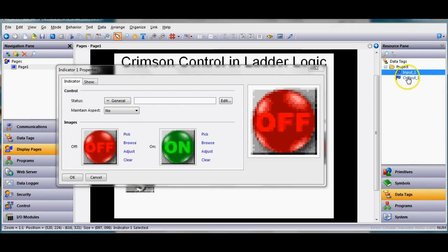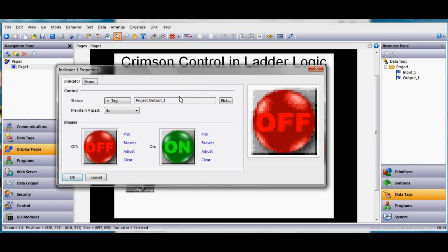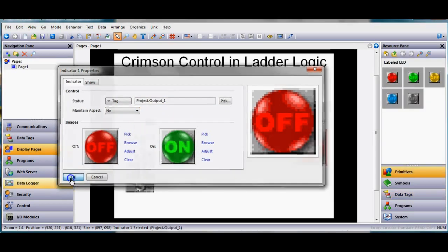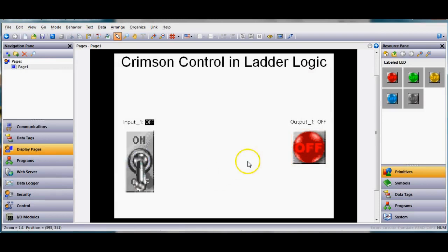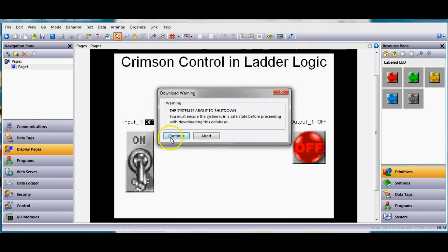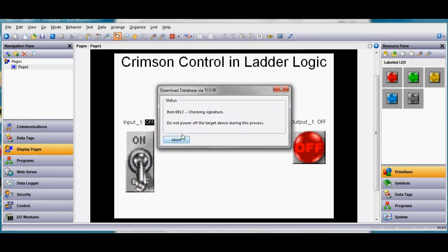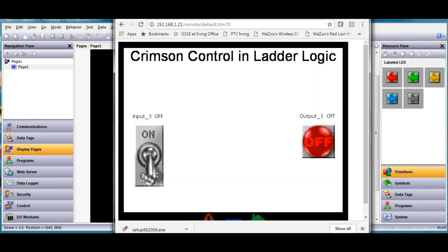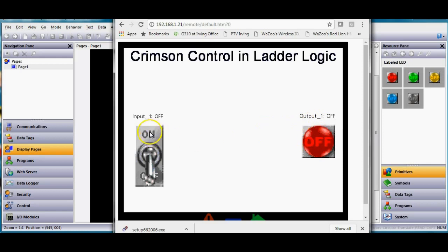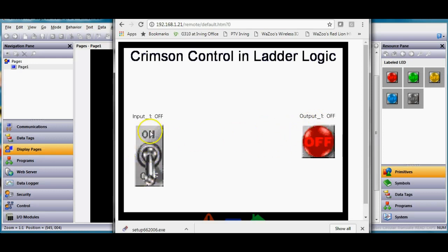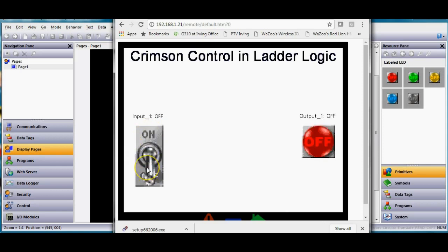And then what I'm gonna do is I need to link this to my output so go to data tags on the right, grab the output tag and drag and drop it right here in the status field. Once I drop it there in the status field I'll click the ok button. I think this looks good, I'm gonna go ahead and download this to my screen, see if it's actually working. The system will shut down as I'm downloading, I've got a web server working as I'm using the new edge controller here and if you look here, here's my logic. If I turn it on, boom, and you can see instantly the output goes on whenever this goes on. That's a pretty simple way to do crimson control for just a ladder diagram.